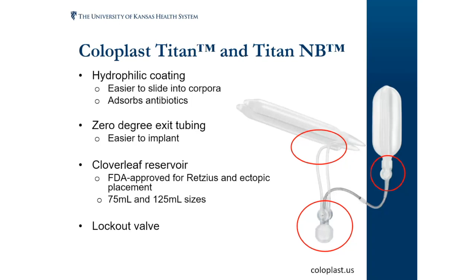There is a lockout valve, which is the rightmost circle. The lockout valve on this device is on the reservoir. Important to know because you're actually able to test the lockout valve when you place it, especially in potentially high pressure situations like ectopic placement. You can gently press on the abdomen with the syringe still in place and see how much back pressure it will take to overcome that lockout mechanism. The last circle I have in here is the pump itself. This is actually one of the newer pumps, the Titan Touch, where you can press the button and the device will deflate itself without having to hold it. The more traditional model, you have to hold onto the actual deflation mechanism. However, some implanters prefer that because the profile of the pump is the smallest on the market.